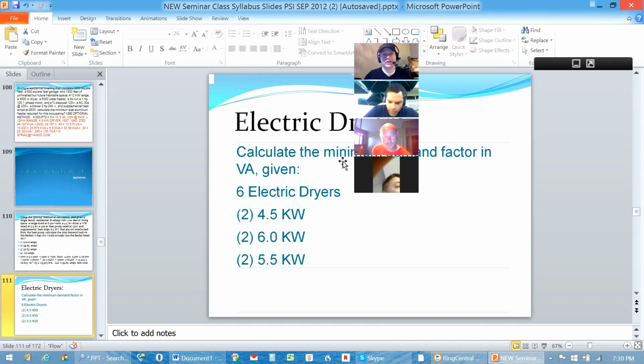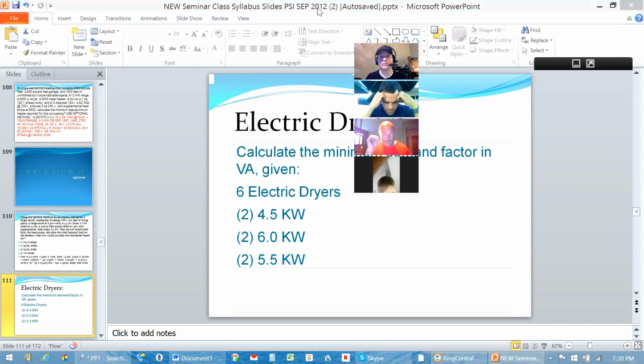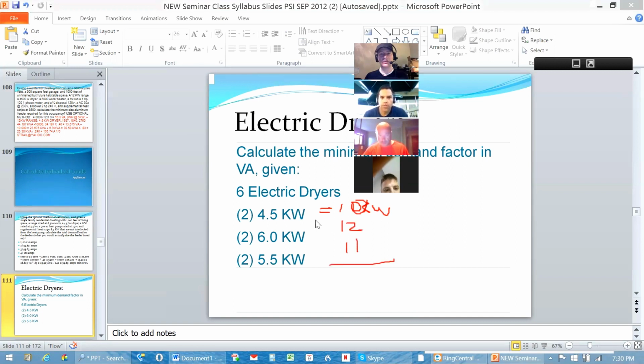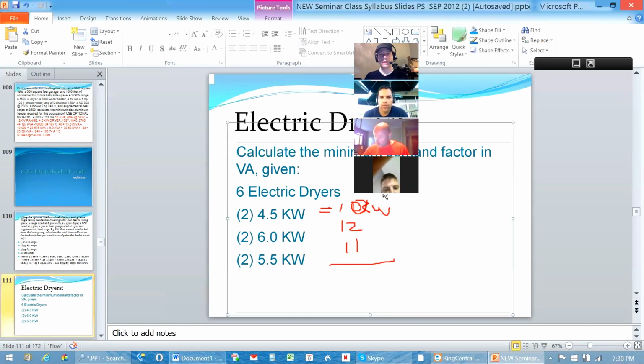So if you had a question like this where you're looking at 6 dryers all together in a residential dwelling, say 6 electric dryers, a pair of them that are 4.5 kW, a pair that are 6.0, and a pair that are 5.5 kW. The only thing to be careful of is that you're taking an uptick on that first pair. I have to have at least 5,000 for both of these. So instead of this being 9 kW, this is going to be 10 kW, okay? And if they don't tell you anything, since there's not a word up here about standard method or optional method, this will be standard method because that's your default. So it's 10K plus 12K plus 11K as your beginning step. So I've got 6 dryers here at a total of 33 kVA.